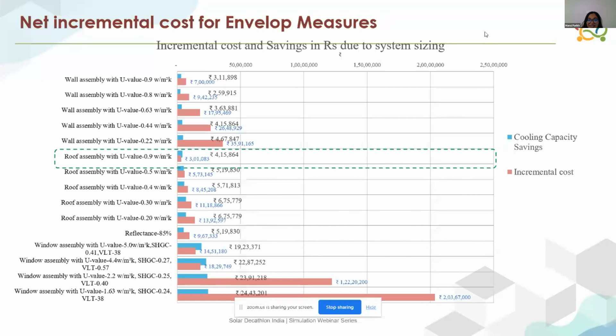So the next step for me is I check the incremental cost for all measures and select the measures accordingly. What you would see is for certain measures, the incremental cost is negative. This means the system sizing saving is higher as compared to the cost of implementation of that particular ECM. So in this case, say for roof insulation of 0.9, the shading 0.9, your HVAC system sizing saving is higher as compared to the cost of insulation. There are certain measures like this, specifically like roof U value, and this happens with shading measures if done correctly. Those ECMs should always be bundled together. So this is how we do the system sizing correctly, as well as start accounting for the cost position. Thank you.